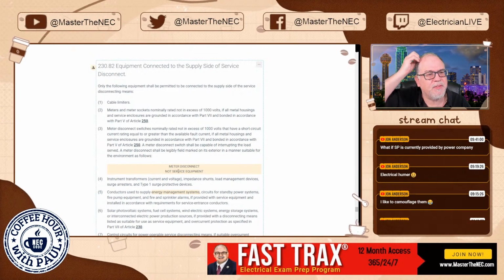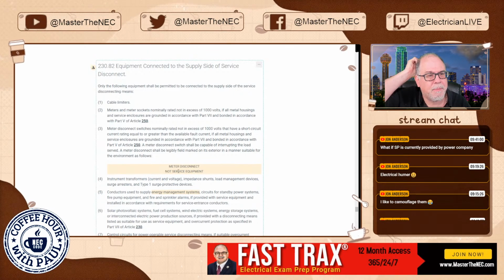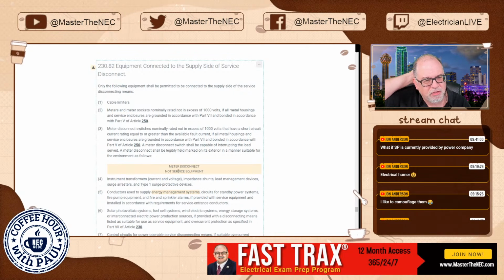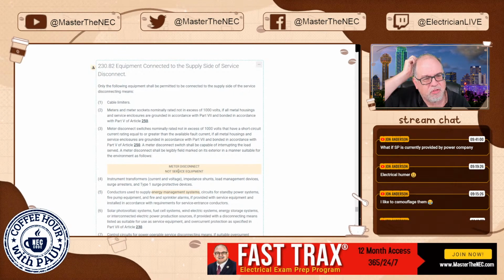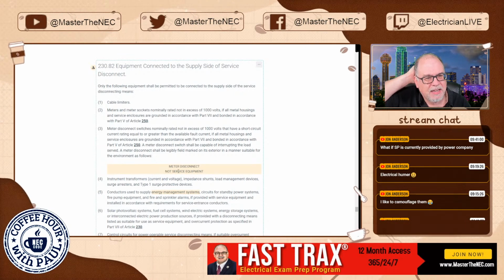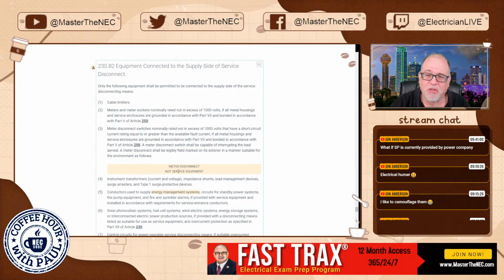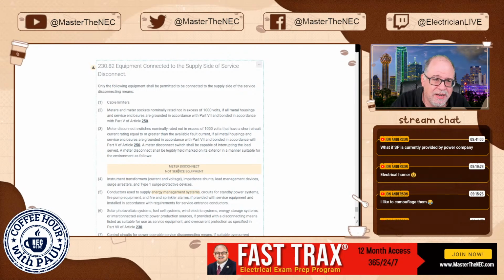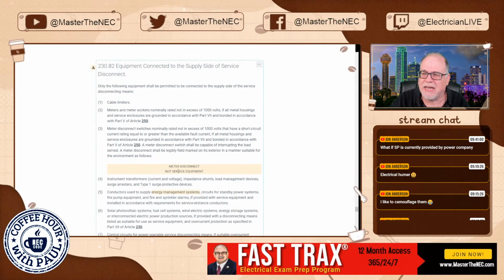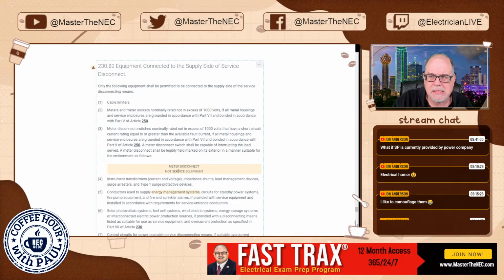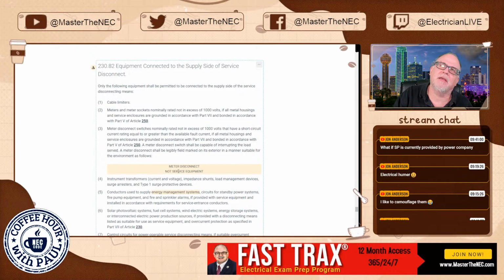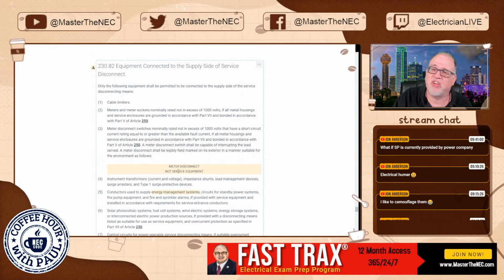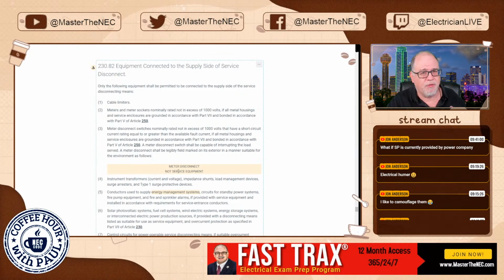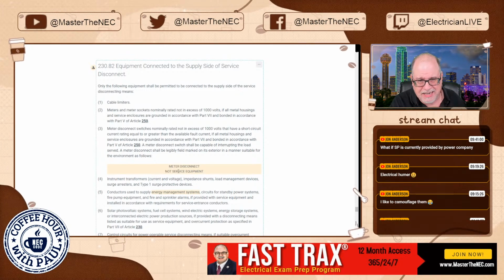John says, what if SPD is currently provided by the power company? John, I'm not sure I understand. Clarify for me. You mean if the surge protective device is already provided? Well, if it's already provided, then it's probably type 1. And if it meets all these rules, then I think it would be okay. Now, you'd have a hard time convincing the AHJ if it happened to be so far upstream that you can't validate it or verify it.